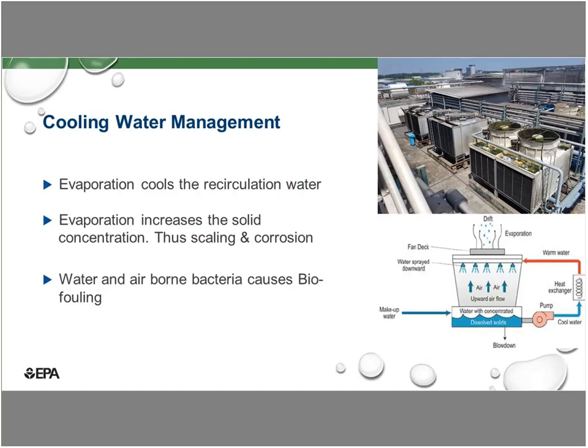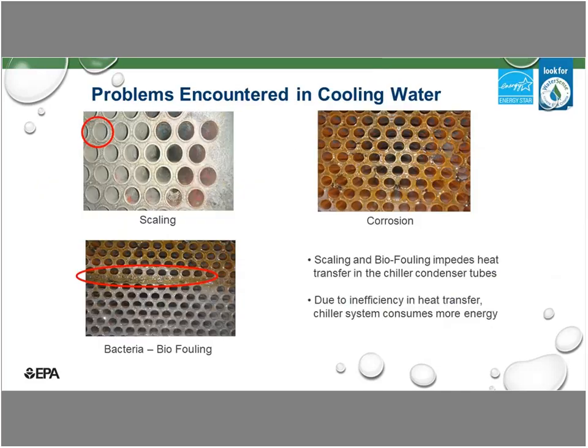Okay. For the principle of cooling, Robbie has already explained very well. When you use evaporation to cool down the water, the minerals in the water concentrate up, and this is where you get scaling and corrosion. And of course, when you recycle water, potentially you will have airborne bacteria causing biofouling as well. This is pretty standard in every cooling tower. These are the three key problems that typically happen: scaling, corrosion, and biofouling.